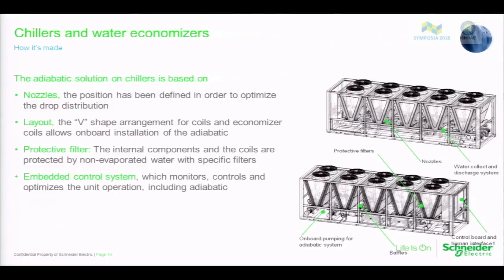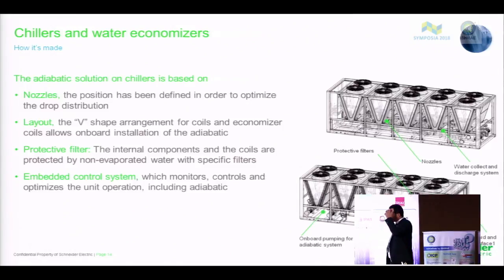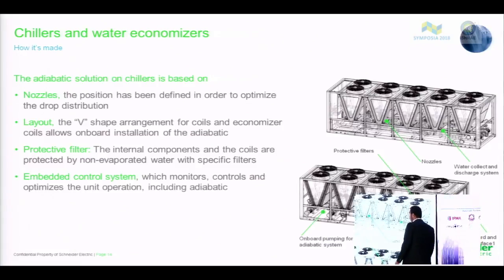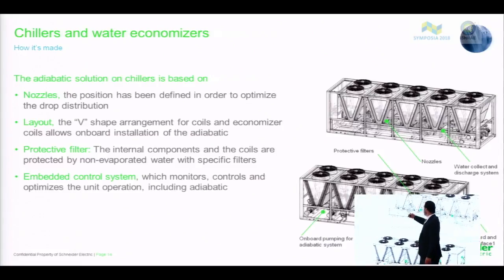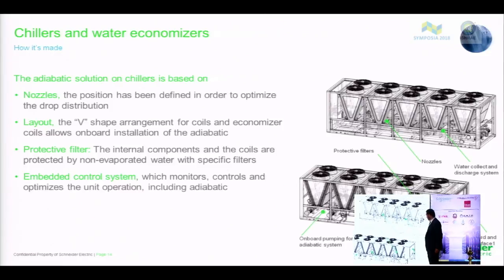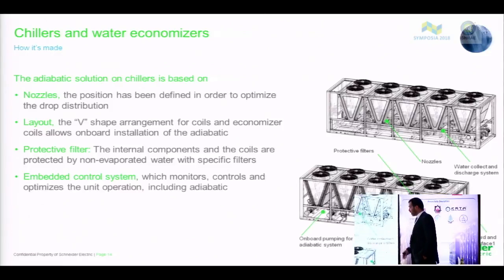On the chiller, the same concept could be applied. The only difference is that on the air economizer, typically, the water is essential to get the capacity. On the chiller, the water is usually applied to boost the efficiency. You can use the water also to boost the capacity, but in the event of water loss, you lose capacity. So our suggestion is to use water only as a booster. So typically, this is an example of one of our chillers, but that's pretty general.